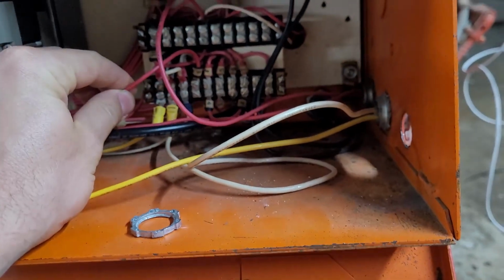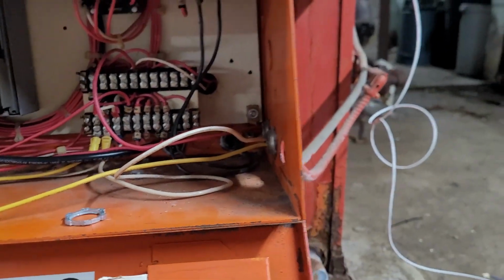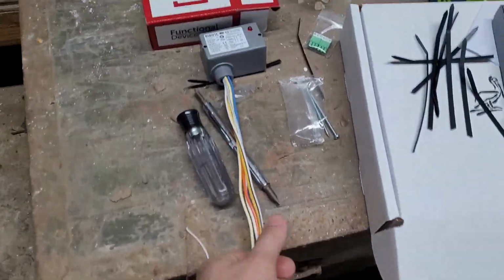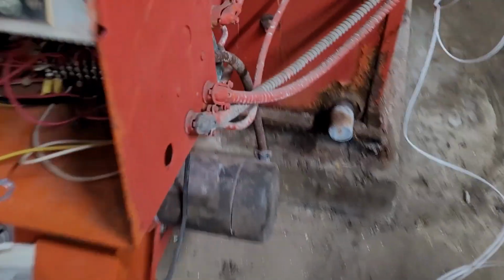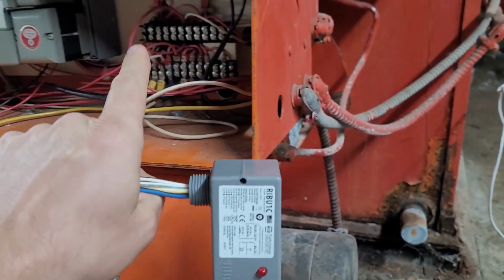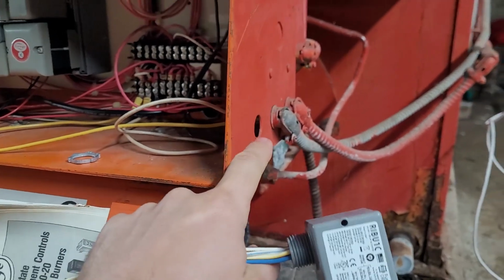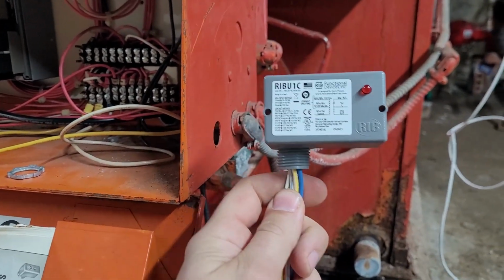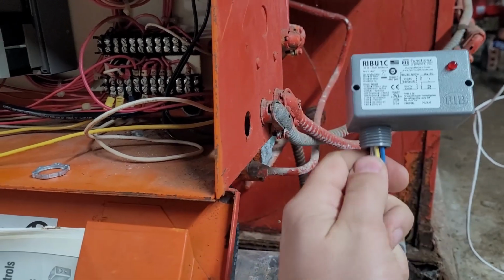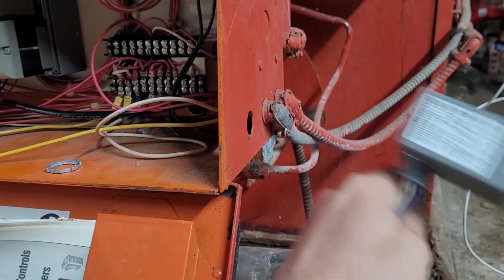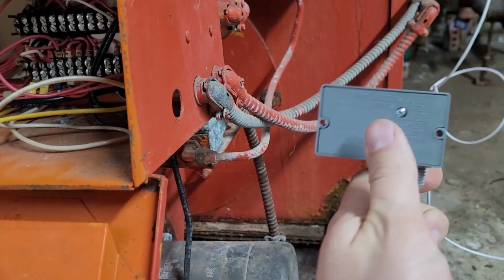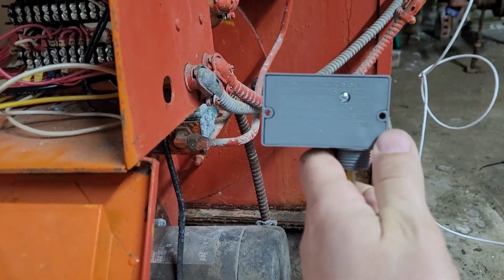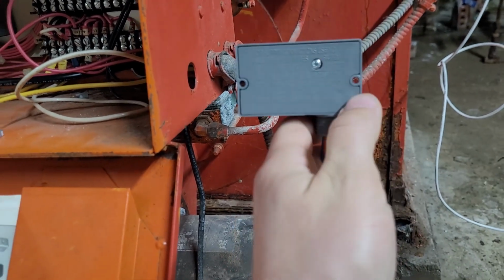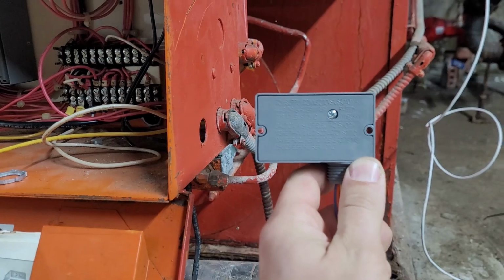So here it is, terminal 3, and I've got a knockout here, so I'm going to use a knockout relay. And I'm going to show you guys a trick with these knockout relays. So we've got the low voltage run from the controller over to the relay location. Now the high voltage needs to be inside the enclosure, but the low voltage does not necessarily need to be inside the enclosure. So what you can do with these, instead of punching an extra hole in this boiler from 1976 and running our low voltage wire inside, you can actually take the back of this relay off and cut out a corner and have the low voltage come out the corner of the relay. So I'm going to do that and I'll show you what it looks like.